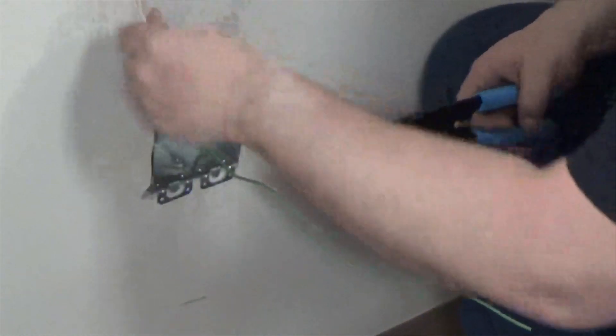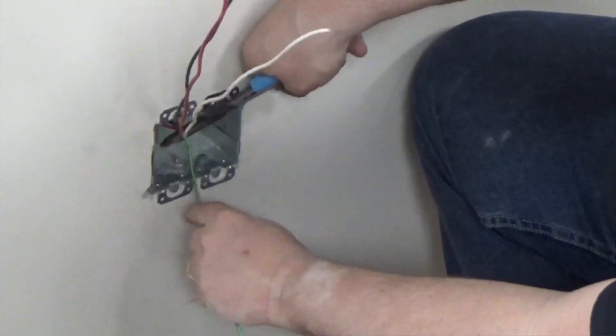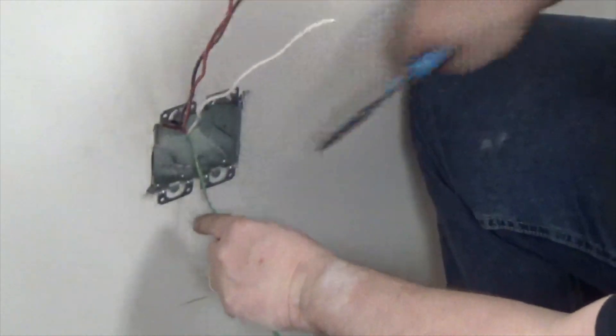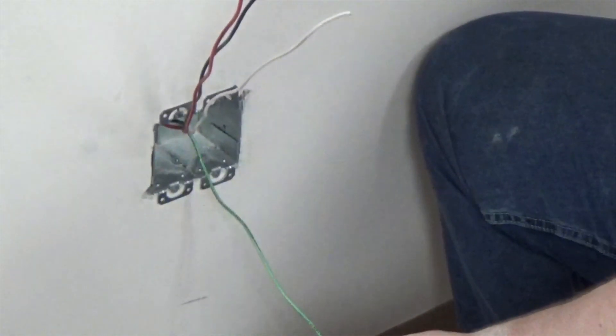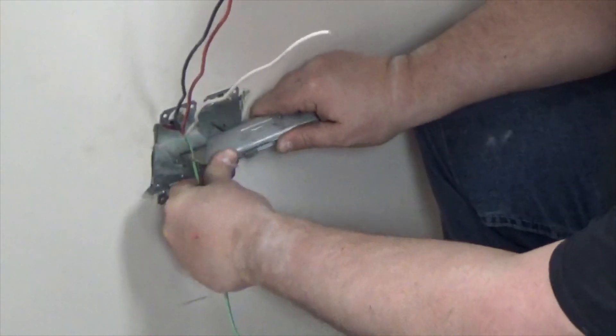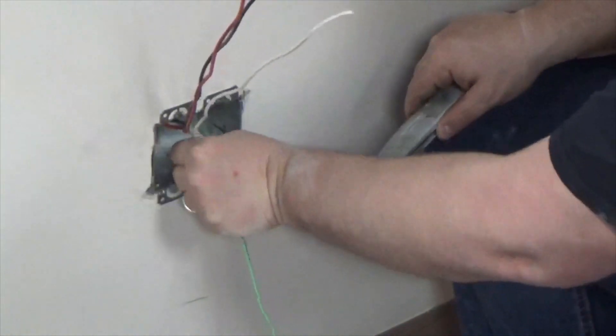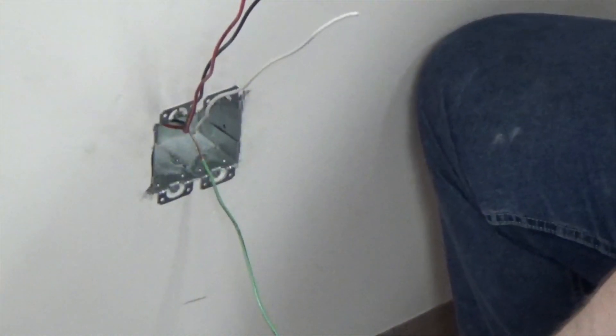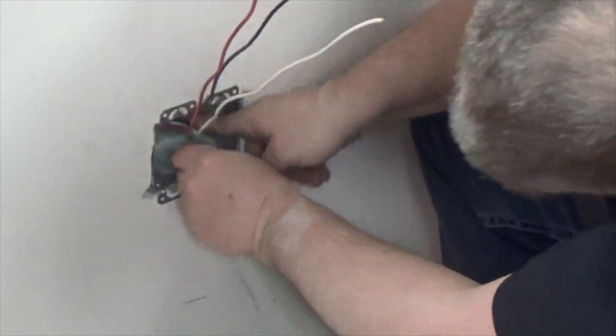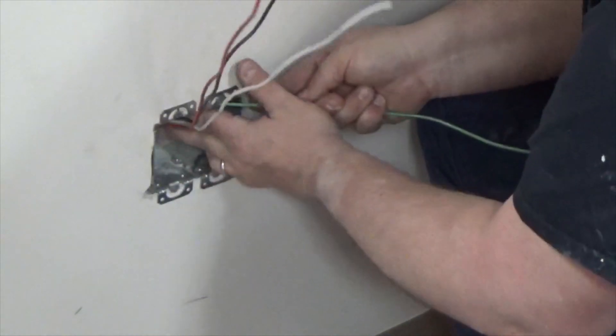Alright, when connecting this, what I'll do is I will cut my green insulation and I'll strip out about an inch or so. Take my razor knife and then I will remove the insulation and then I will wrap it clockwise around my ground screw. And my box will be grounded.